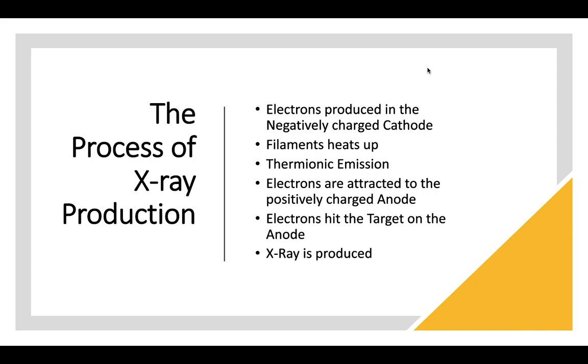The most common would be a rotating anode, and it can rotate due to an induction motor. Then it flows through the anode and hits the focal track on the tungsten target. Then the selected effective focal spot gets directed to the patient, and lastly the image receptor to form an image.